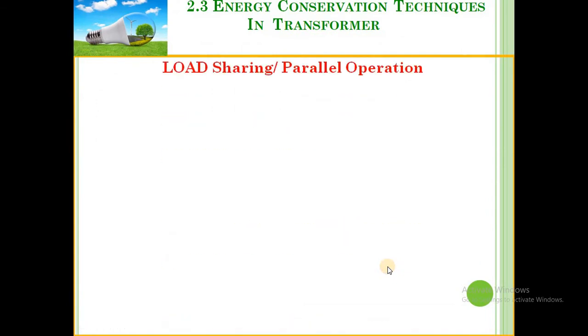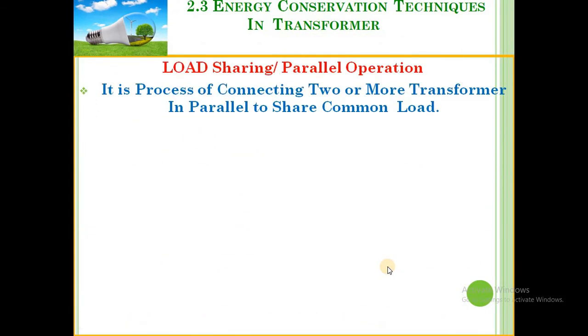So next, load sharing or parallel operation. What is load sharing or parallel operation? When two or more transformers are connected in parallel, it is known as a parallel connection, and the parallel connection is done to share a common load. Means to share a common load we can connect two or more transformers in parallel.